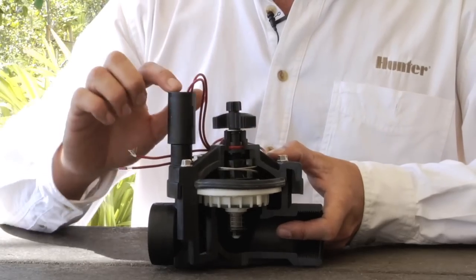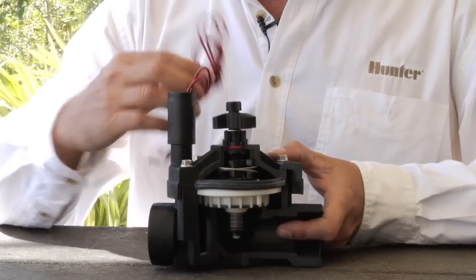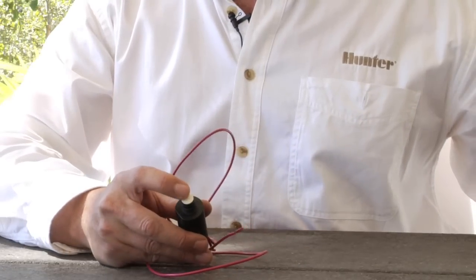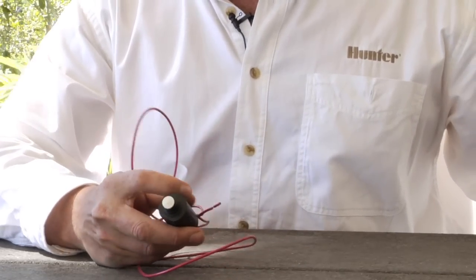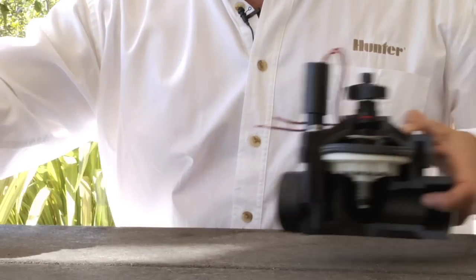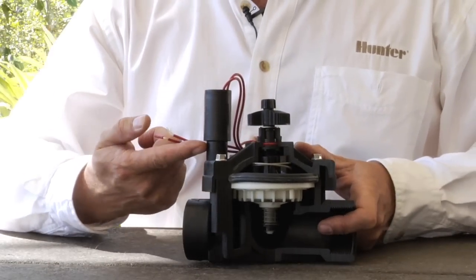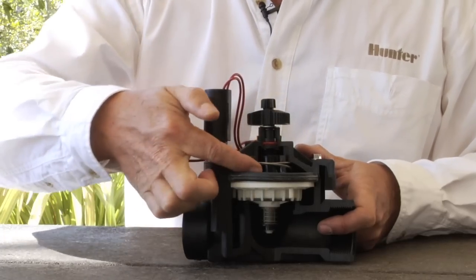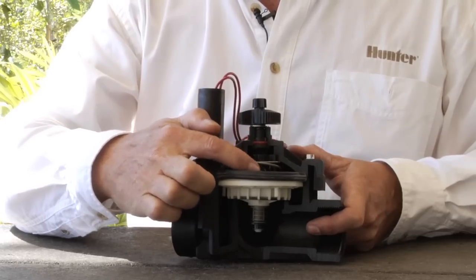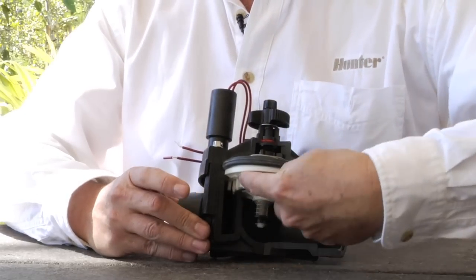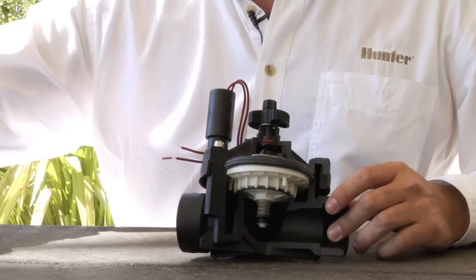Beyond that, we have the solenoid, and that's what receives the electricity from the controller. The solenoid has a plunger on the bottom. When it's electrically activated, the plunger will raise up. And when it raises up, that little rubber gasket comes off of its port and allows the water to go down the exhaust port, thus decreasing the pressure on top of the diaphragm, allowing the diaphragm to move up and allowing the water to flow out to the field.